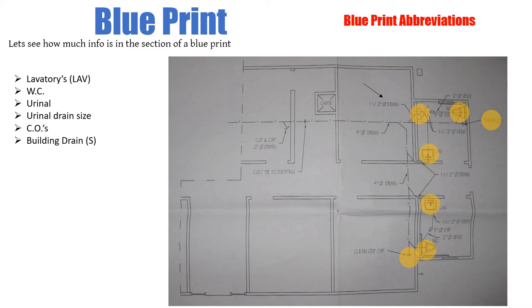The building drain? Well, in this case the building drain is represented by an S. Now it looks like a five almost, but all along here you see all these S's. So that's representing the building drain all the way out here, which is the main drain that carries away all the sewage from the washrooms. Here it's indicated with an S and even gives you the size of it, four inch.